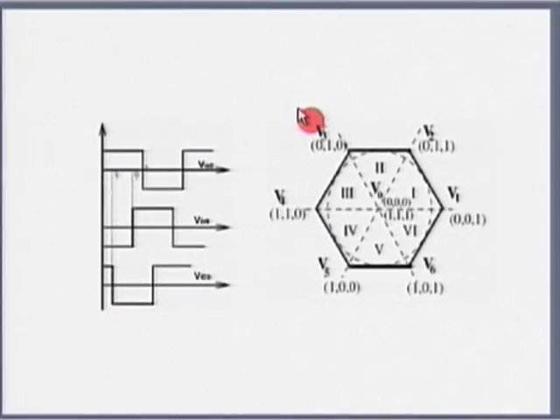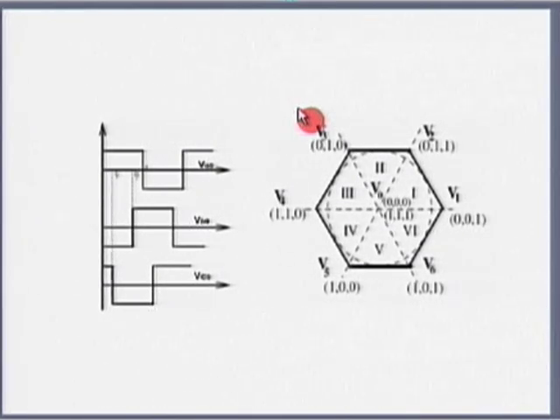If I take the Fourier series of this waveform, the harmonic spectrum is going to be 6n plus or minus 1. If I want a 50 hertz supply, the predominant harmonics are going to be 250 and 350 hertz; the 11th harmonic is going to be 550 hertz.